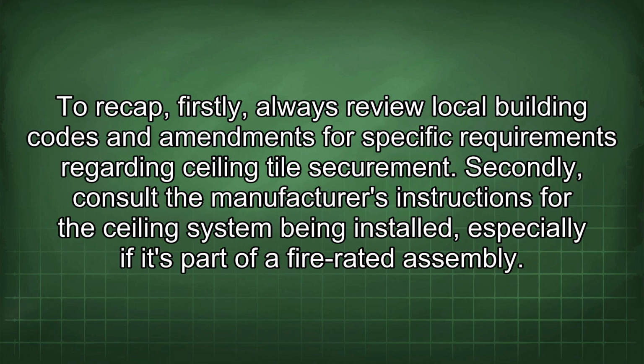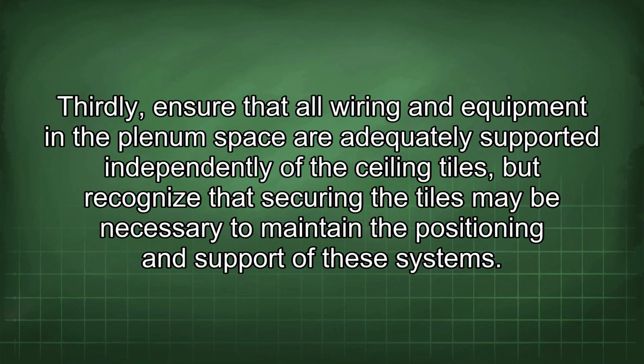To recap, firstly, always review local building codes and amendments for specific requirements regarding ceiling tile securement. Secondly, consult the manufacturer's instructions for the ceiling system being installed, especially if it's part of a fire-rated assembly. Thirdly, ensure that all wiring and equipment in a plenum space are adequately supported independently of the ceiling tiles, but recognize that securing the tiles may be necessary to maintain the positioning and support of these systems.